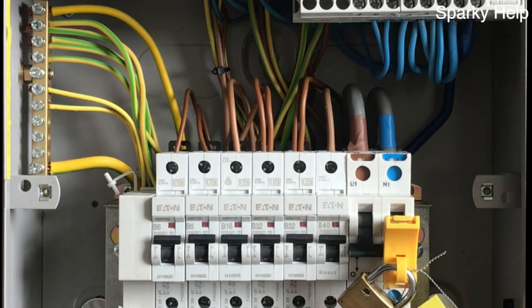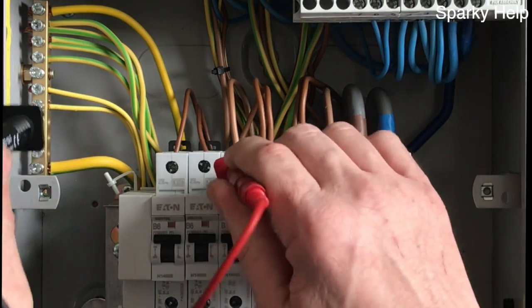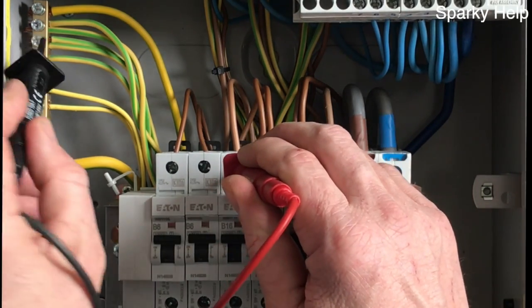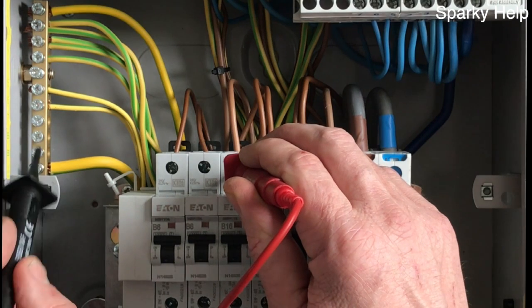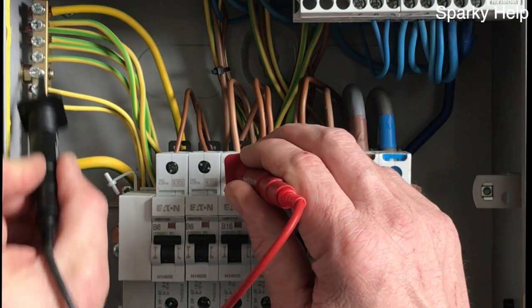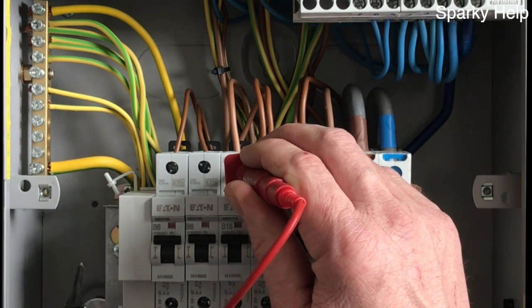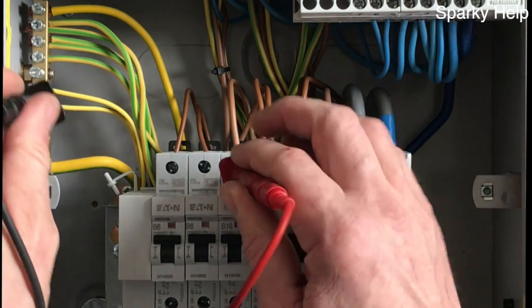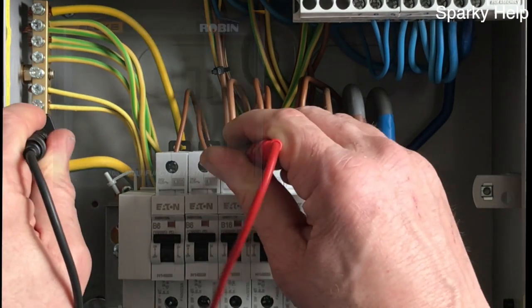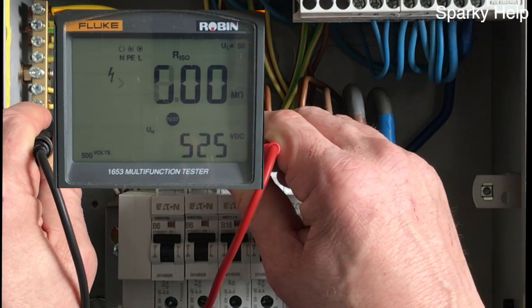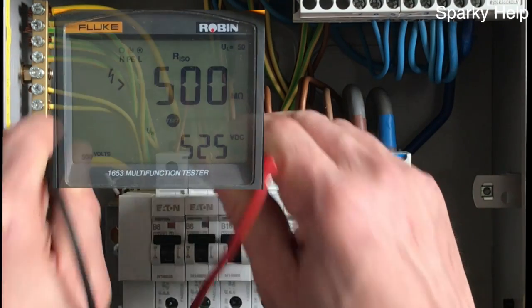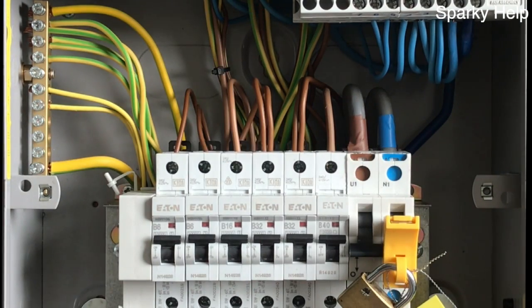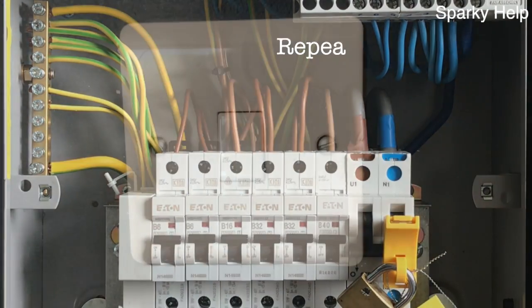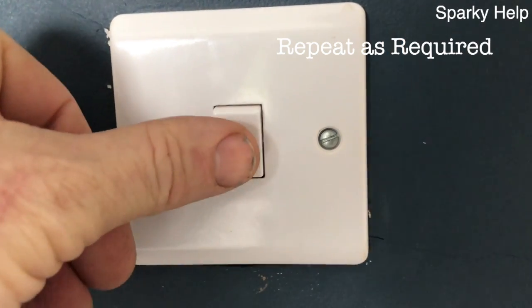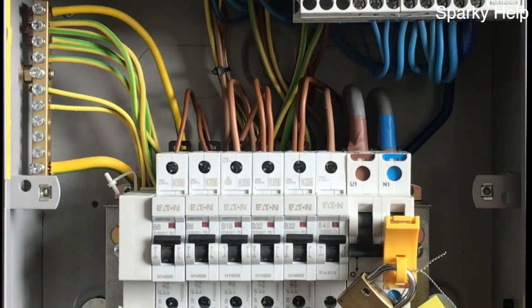Now we go round and we now test lines to earth, and remember, as it says in the regulations, it should be connected to the earthing system, so everything must be connected to the earth, to the installation itself. And then go around and operate the switches again. Make sure you're pressing all your two-ways and your intermediates, and all switches are turned on again.